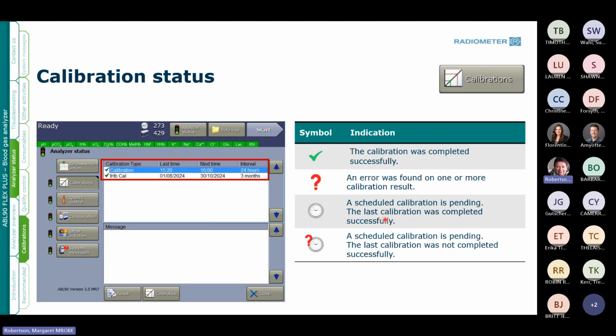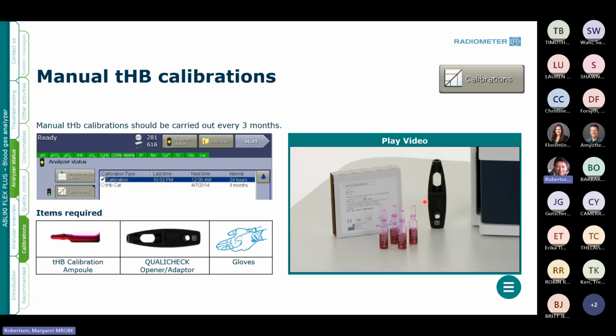If it shows you a little clock, it's letting you know the scheduled calibration is pending, and the last calibration was completed successfully. If it shows a clock with a question mark beside it, a scheduled calibration is pending, and the last calibration was not completed successfully. At this point, you can click on the result button, and it will bring up the result of the calibration, and then you can look and see what happened.